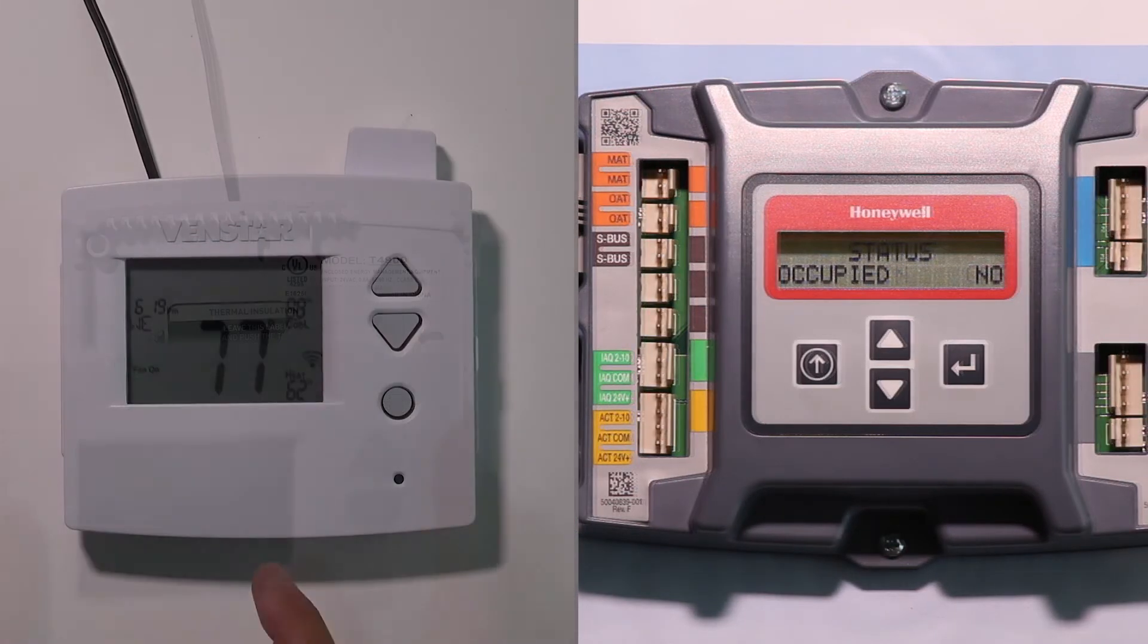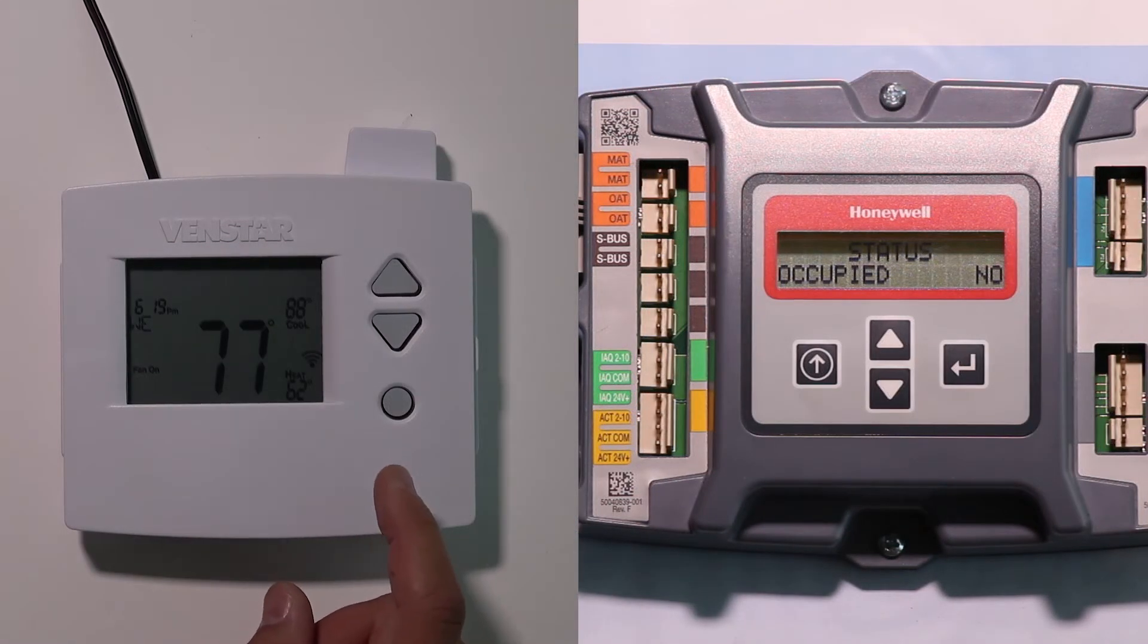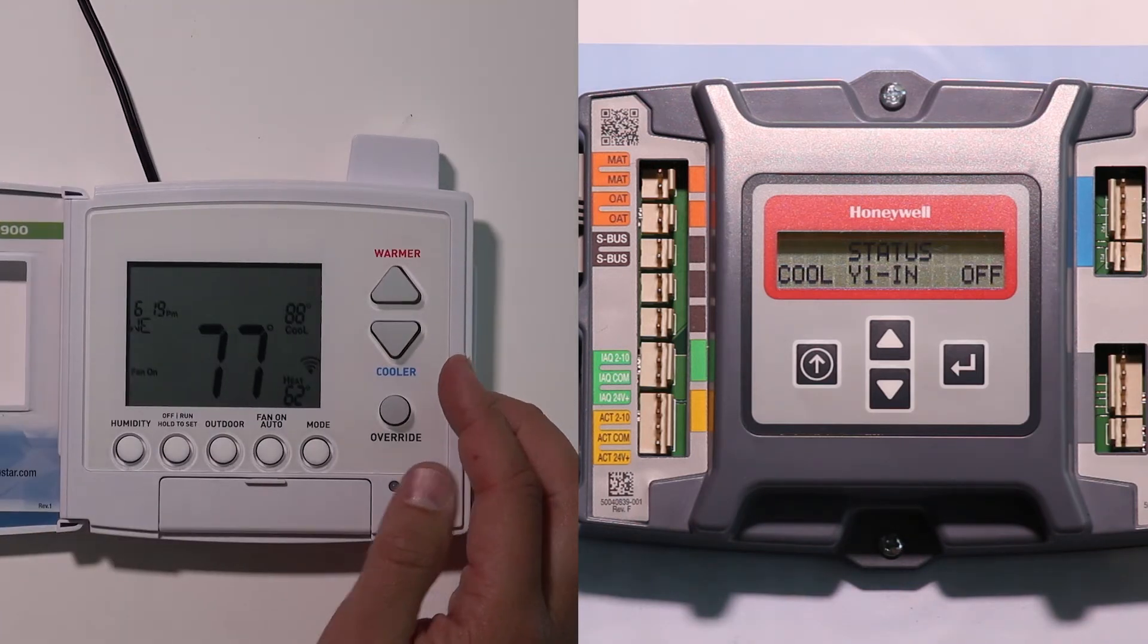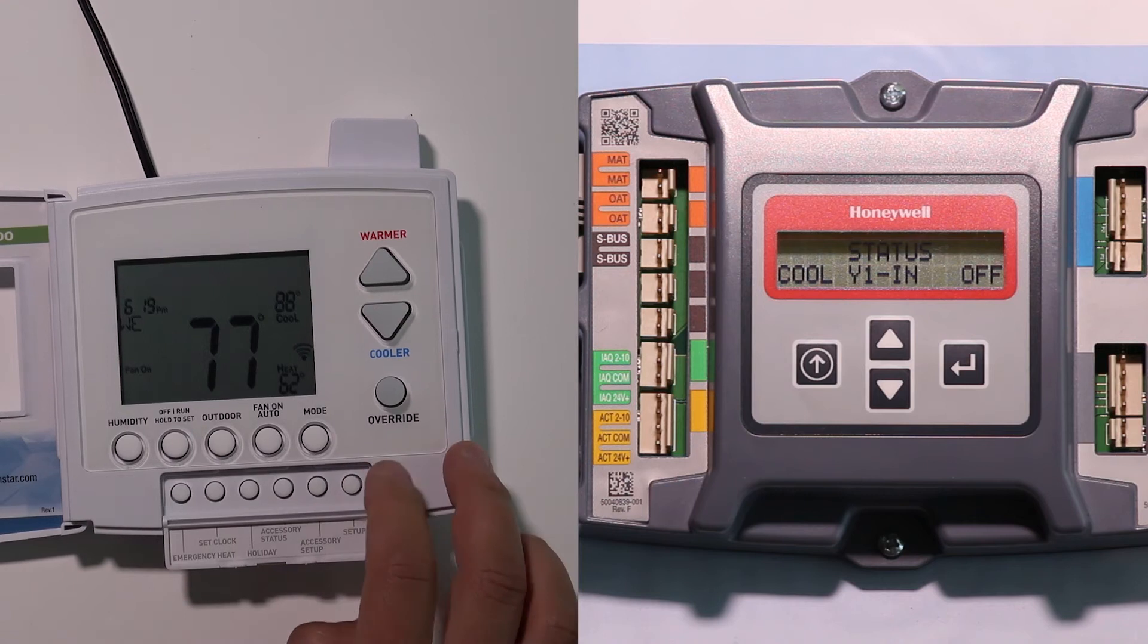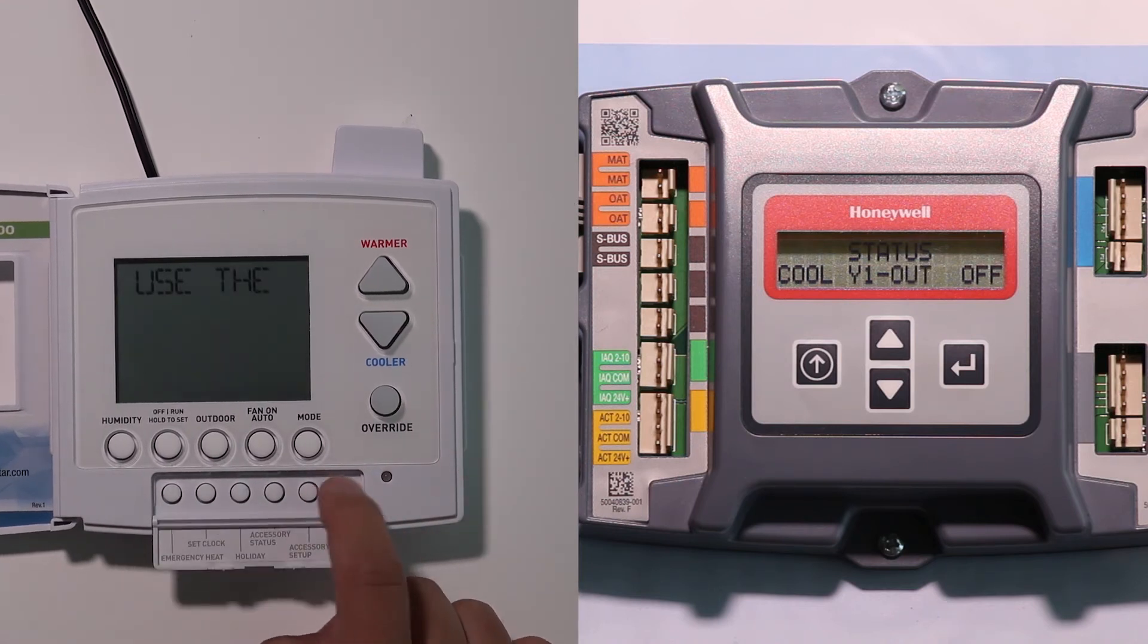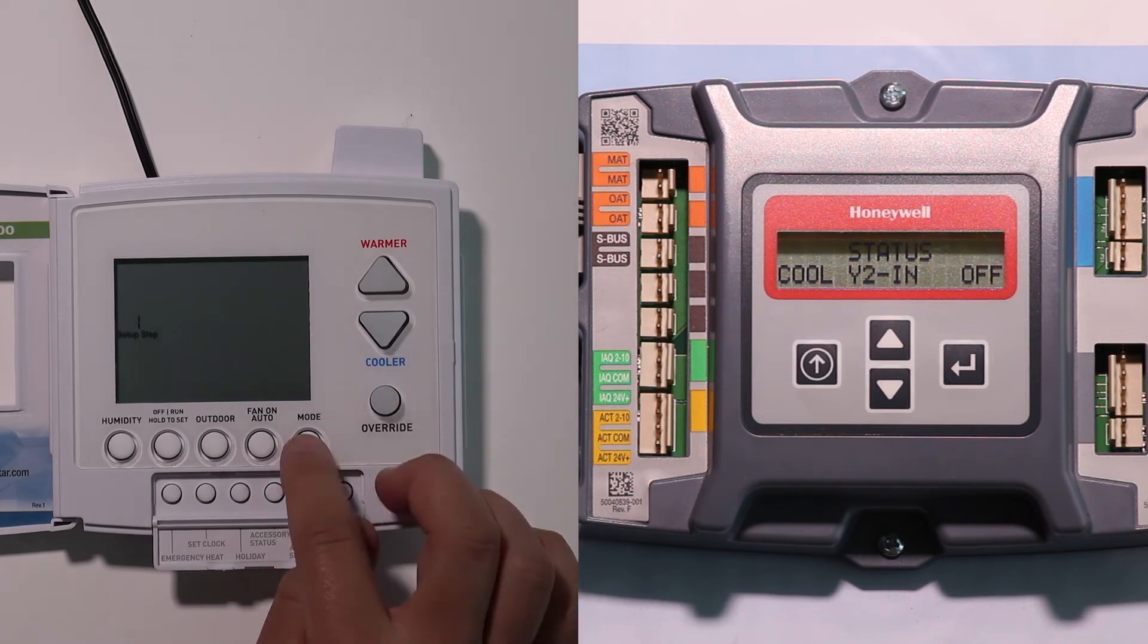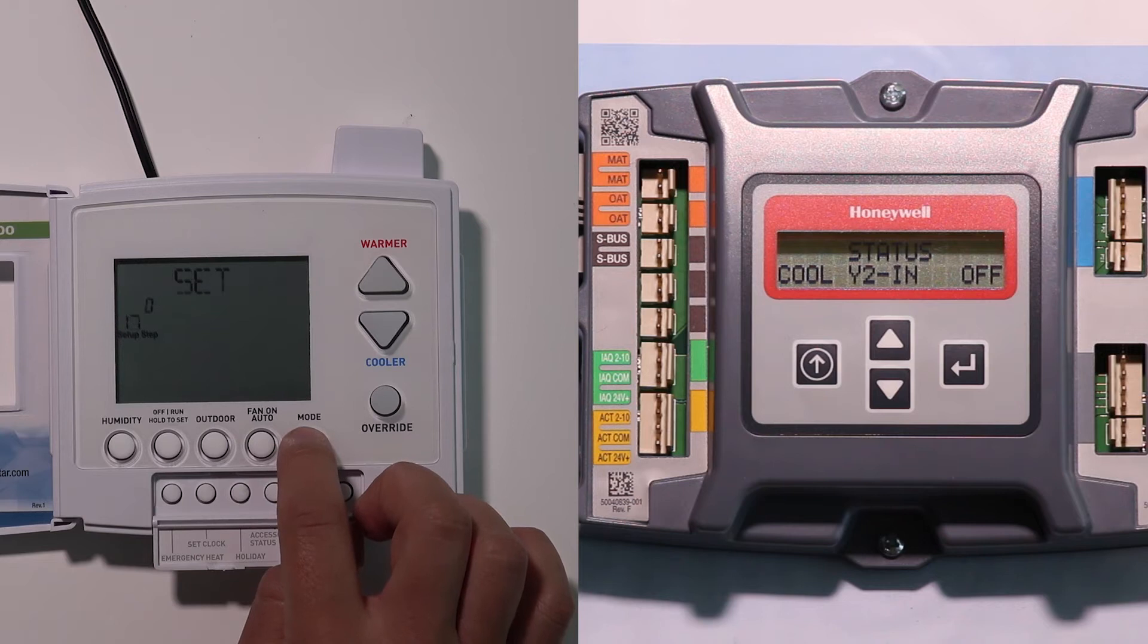Once we have these two components physically wired to each other, then we need to set them up to actually do what we need. So on the thermostat, we're going to go to the setup button under the little door down here. That tells us to use the up and down warmer buttons, and we can use the mode button to toggle up to the settings that we need. There's two settings we're going to look at for the occupancy: one is setting 54 and 55.